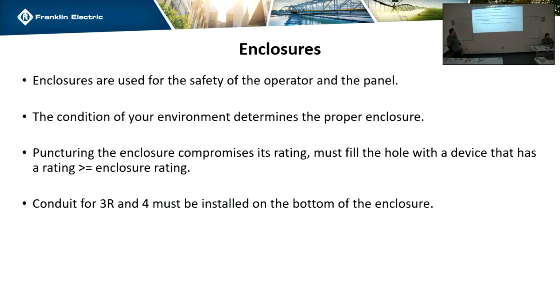All right, for the enclosures, just some general reasons why you would put it in an enclosure. You want to keep everybody safe. The enclosures do a pretty good job of containing any sort of small bursts or fires or whatever. The environment is going to determine it. We have NEMA 1, NEMA 3R, NEMA 12, NEMA 4, and NEMA 4X, all dependent on the environment, and 4X is usually for corrosion or hazardous environments.